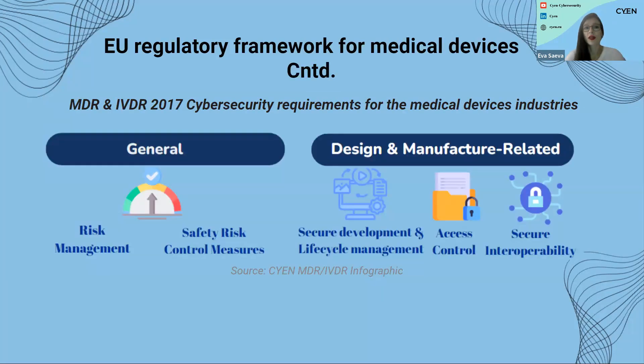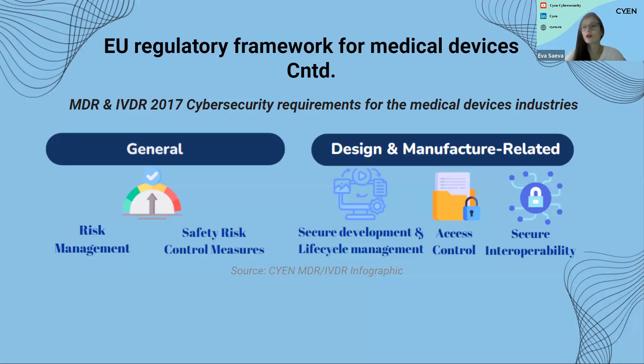What are the cybersecurity requirements under the MDR and the IVDR? These are two sector-specific regulations that clearly regulate other aspects beyond cybersecurity. The cybersecurity requirements here are divided into two sections: general and design-and-manufacture related. The general requirements include risk management and safety risk controls. The design and manufacture related requirements include secure development and lifecycle management — particularly important because each medical device's level of cybersecurity needs to be guaranteed throughout its whole lifecycle — as well as access controls.